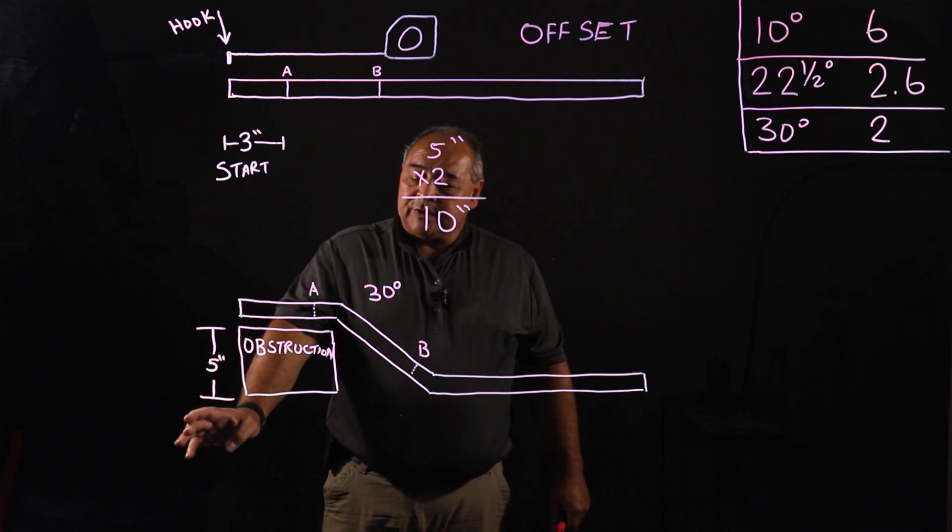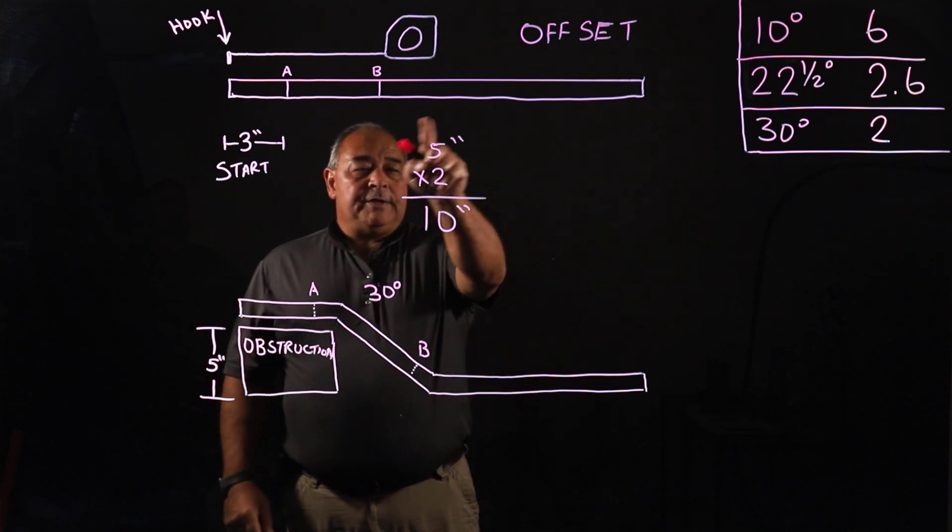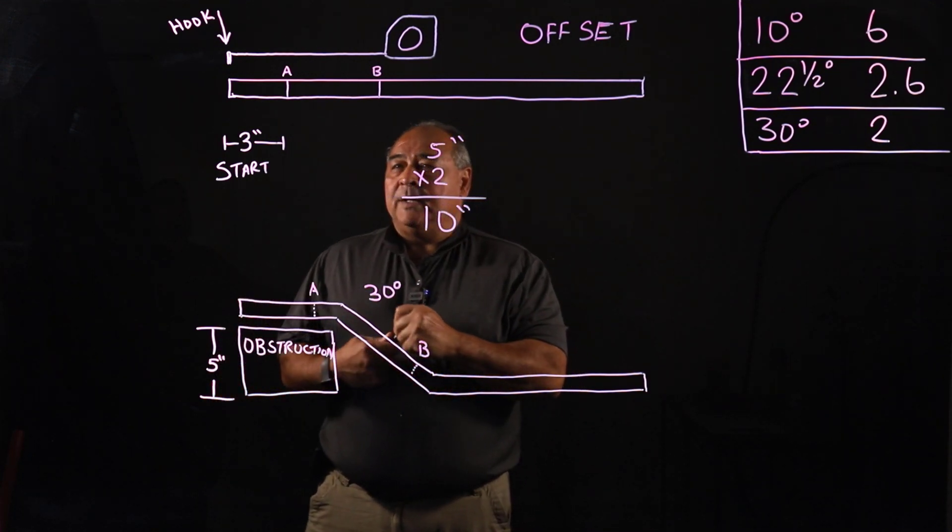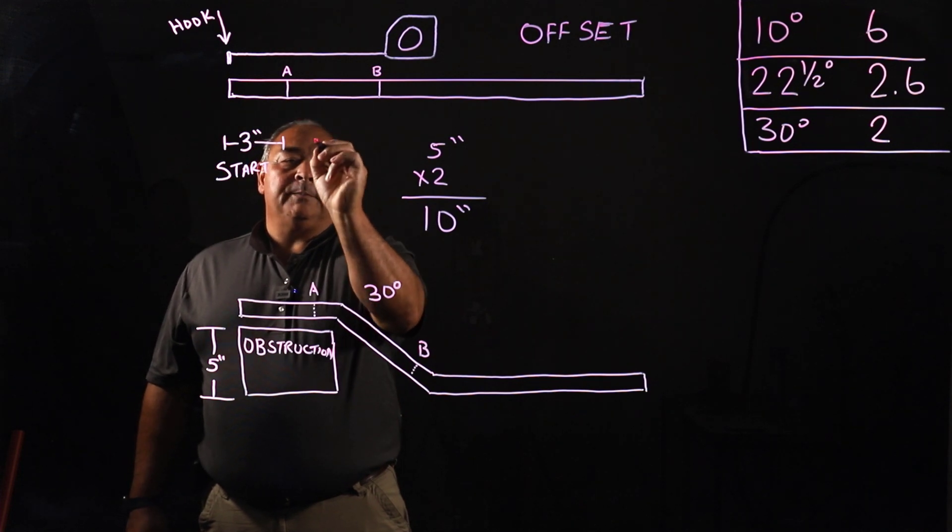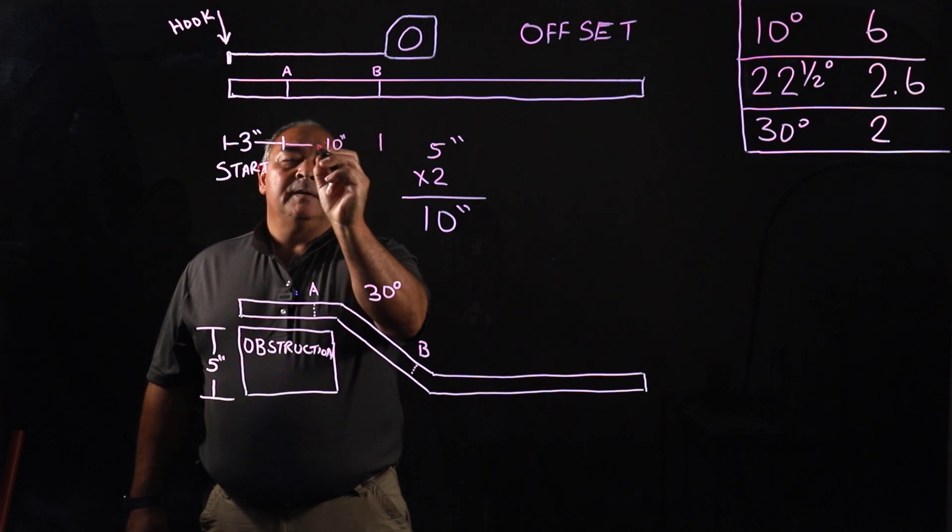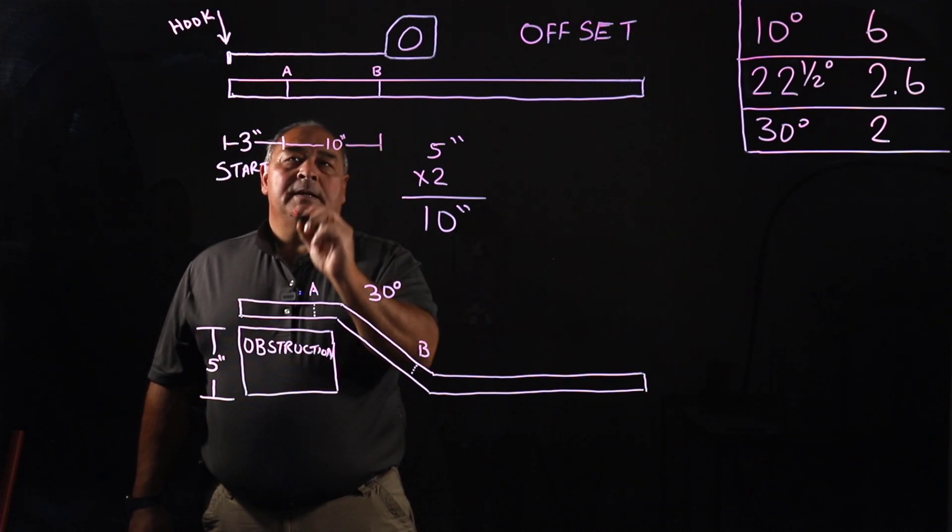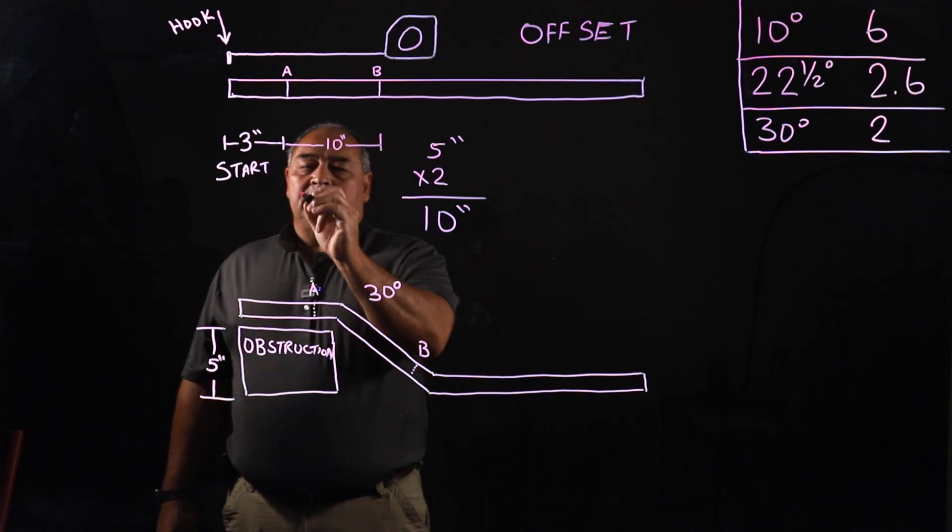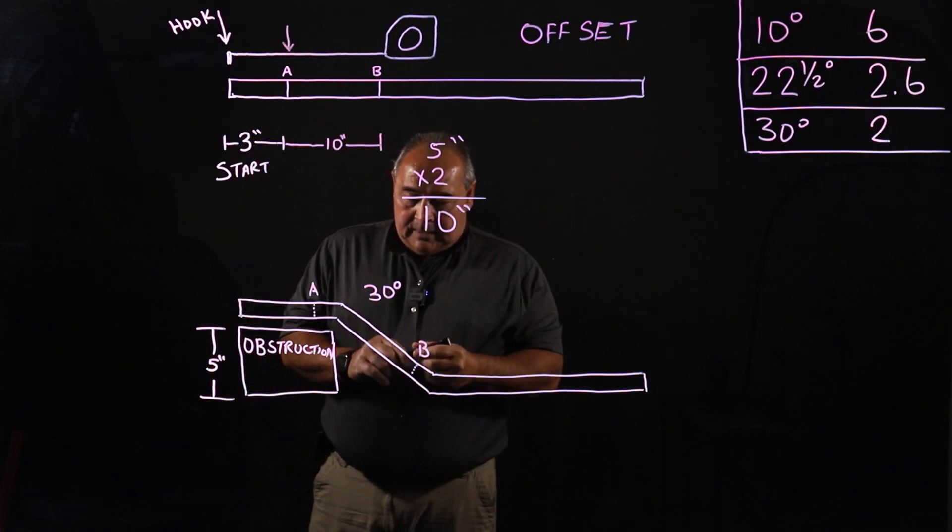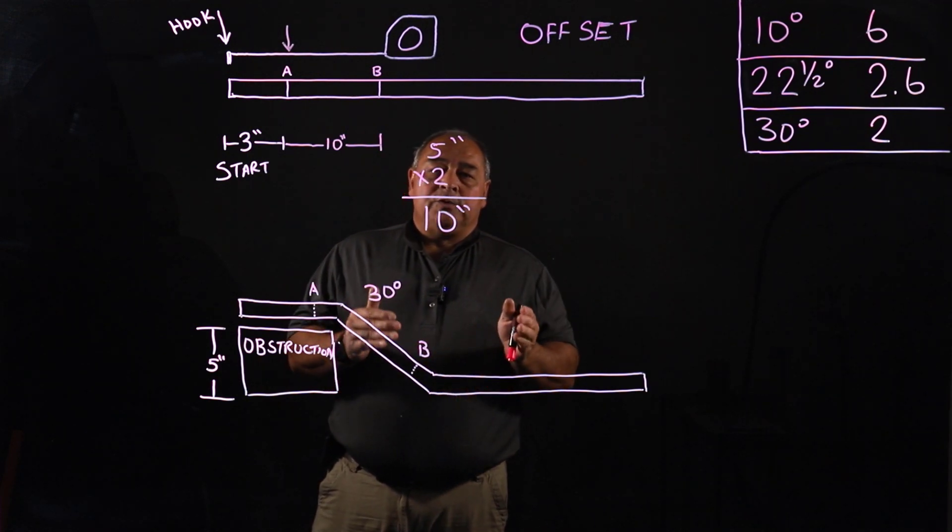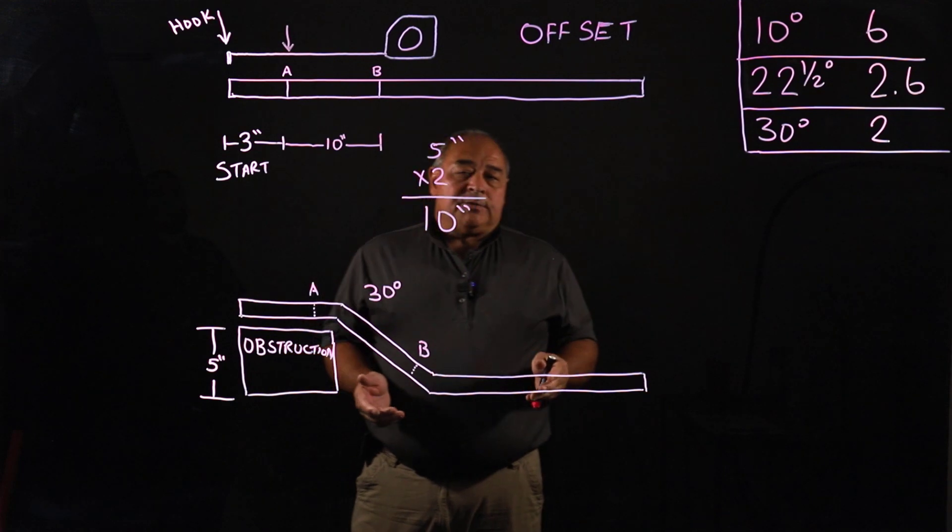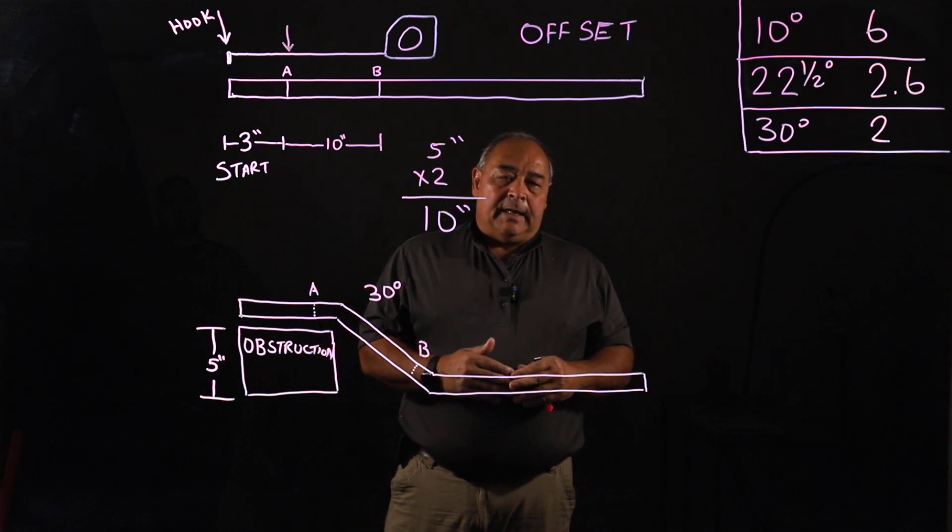For this five inch obstruction that we're looking at, our multiplication was five inches times two, which is 10 inches. So from mark A to mark B would be 10 inches. And everything references off of mark A. That is one thing that in all kinds of bending, once you establish where mark A is going to be, all other measurements refer back to mark A.